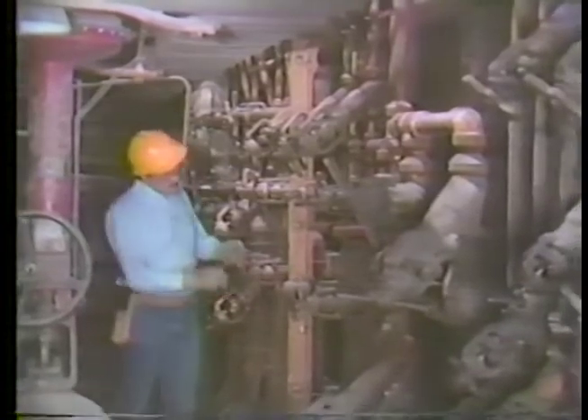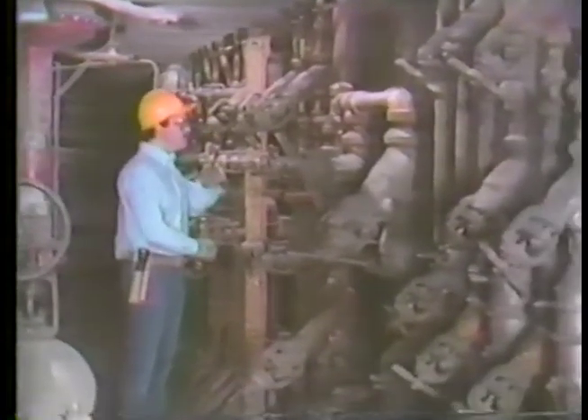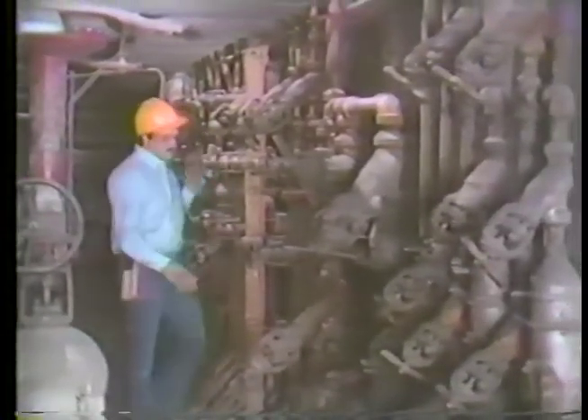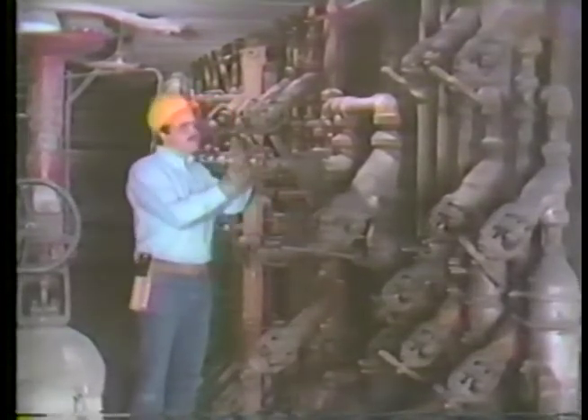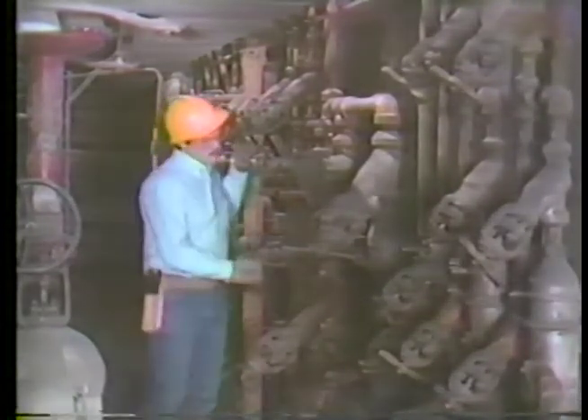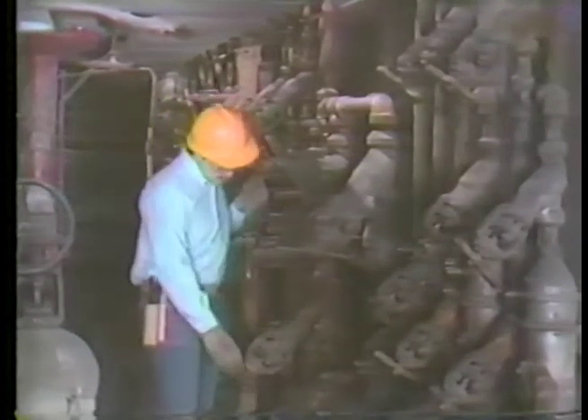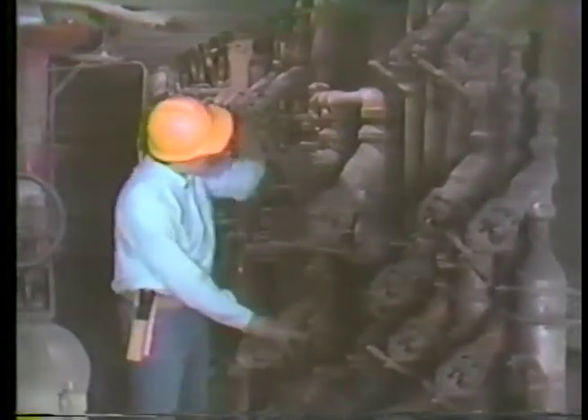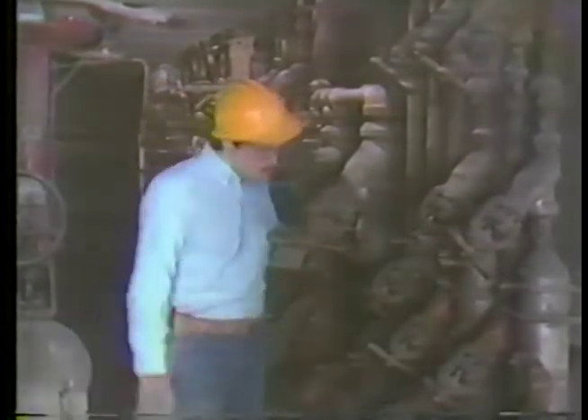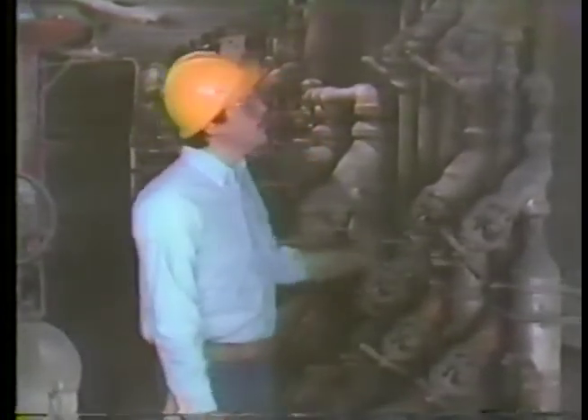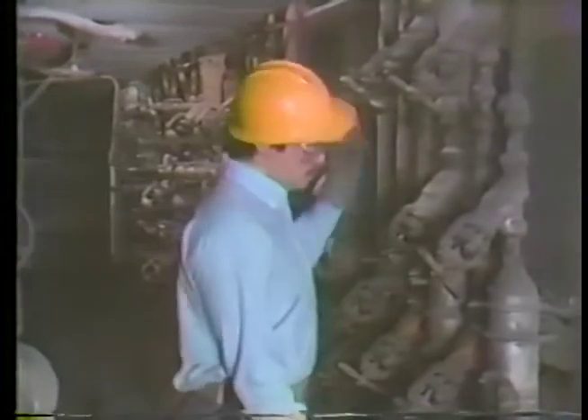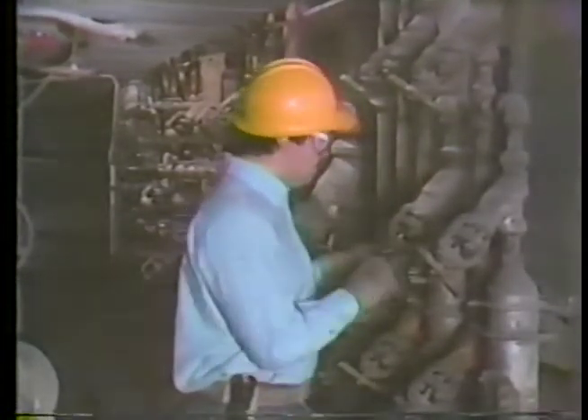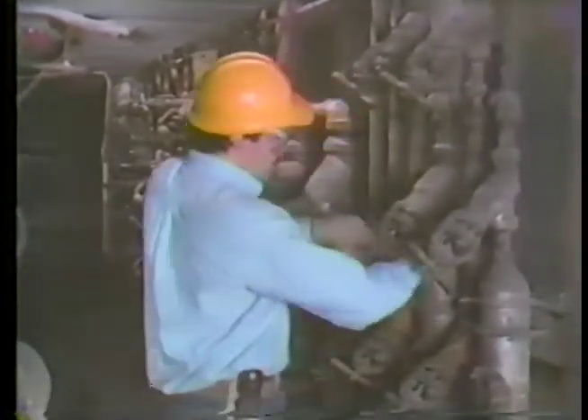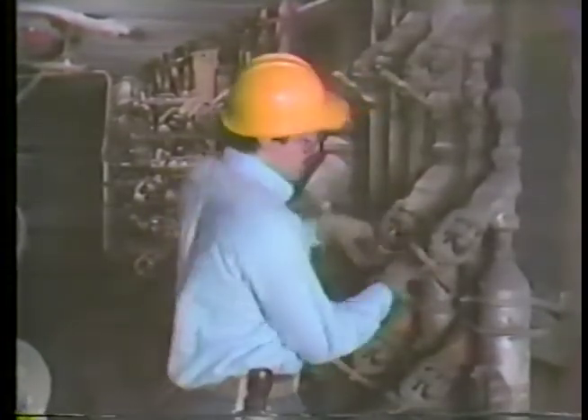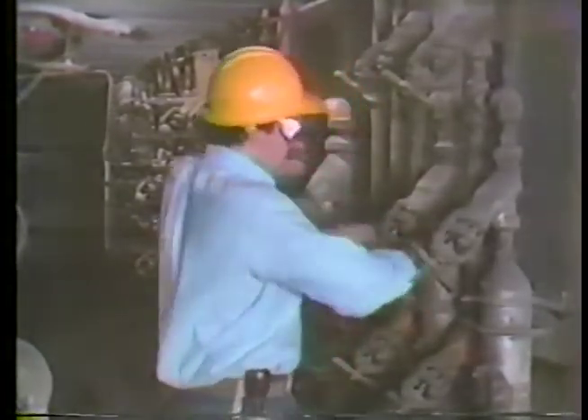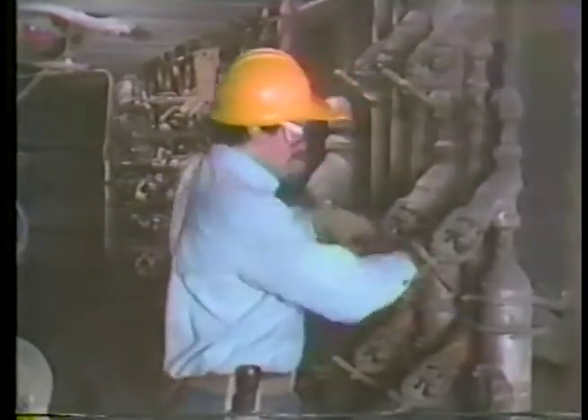During startup, an adequate flow of water, fuel, steam, and air is necessary to establish combustion and to protect components from the effects of heat and pressure. An improperly positioned valve could prevent fuel or air from getting to the burners or cause a pipe to rupture under pressure. By walking the system and making sure all valves are properly positioned according to your procedures, you ensure that the boiler and plant personnel are protected.